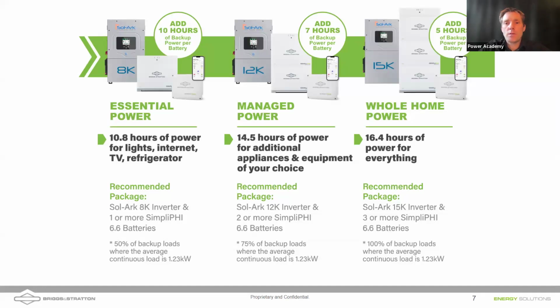And a 15K Sol-Ark. And one of the advantages of that 15K Sol-Ark is it has 200 amps of pass-through, meaning it can allow 200 amps of continuous 240 volt AC current to run from the grid connection through to the loads. Now, that doesn't mean the inverter itself is capable of supplying 200 amps at 240. That inverter is capable of surging to 100 amps, but it can provide 50 amps of continuous power.